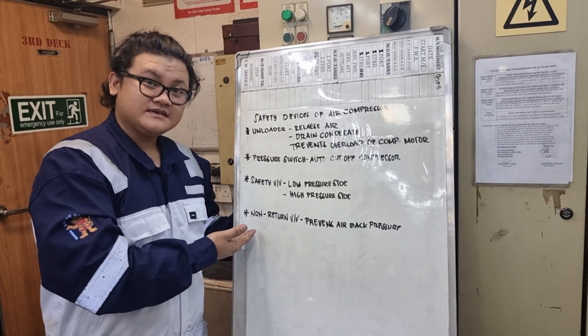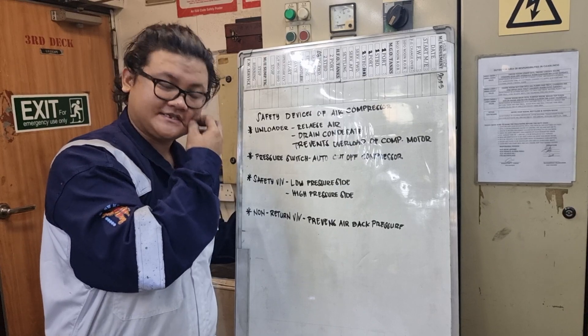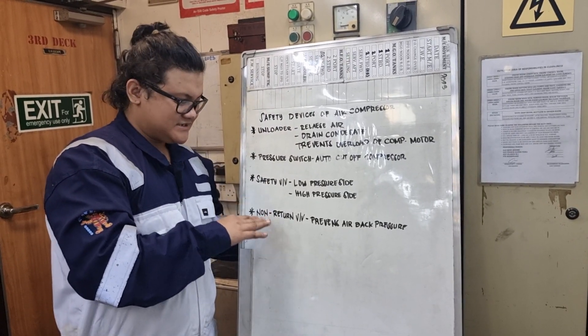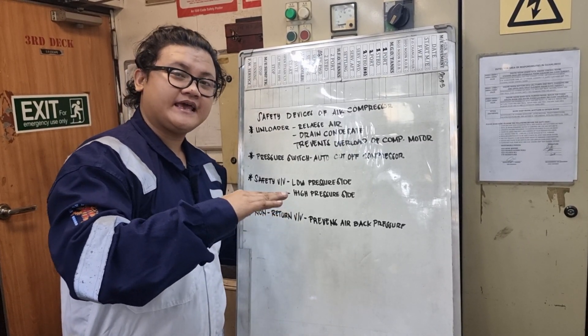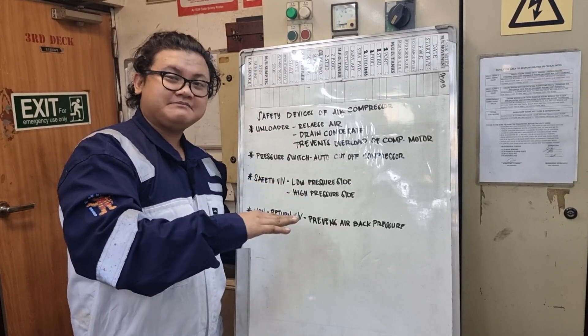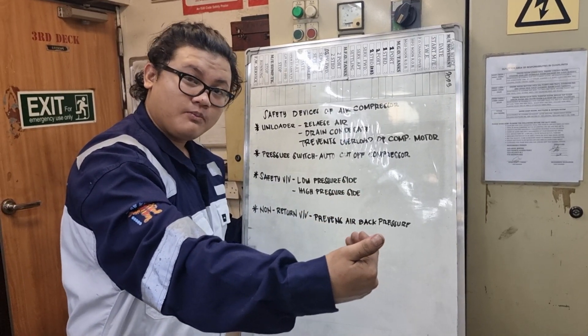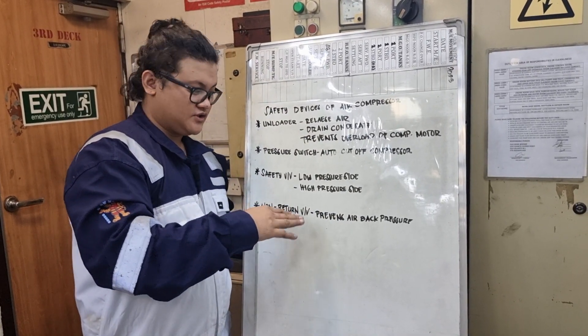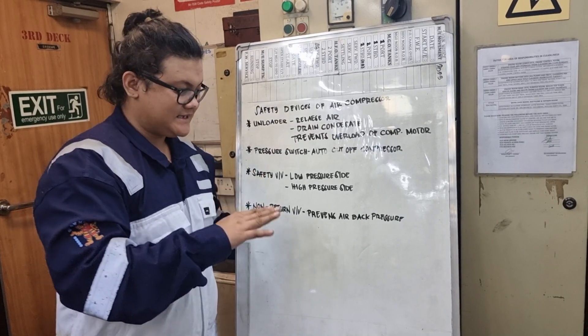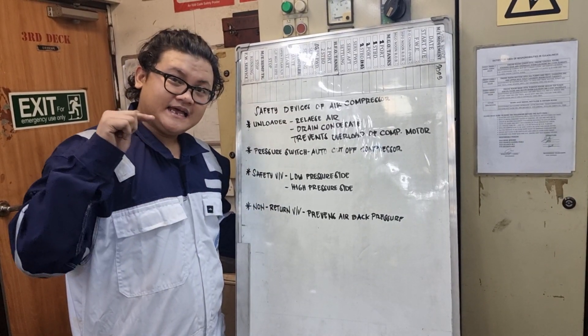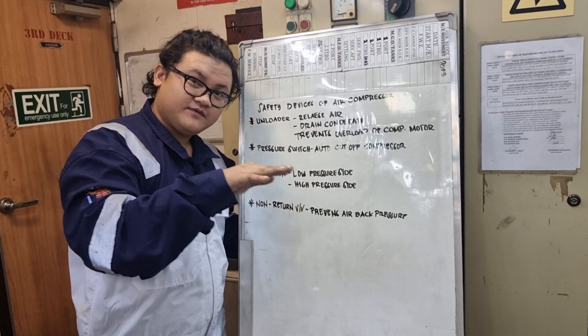Fourth one, non-return valve. This valve is located at the discharge side of the compressor. Once the compressor starts supplying air to the air bottle, there's a possibility that there will be back pressure of the air that might go back to the compressor. So that's the reason why non-return valve is installed — to prevent it from happening. Non-return valve only allows one direction of the air flowing in that valve.